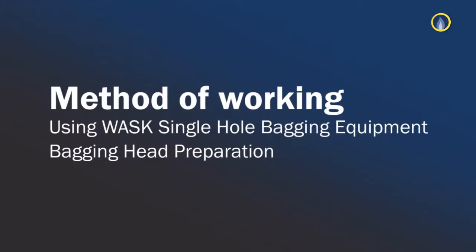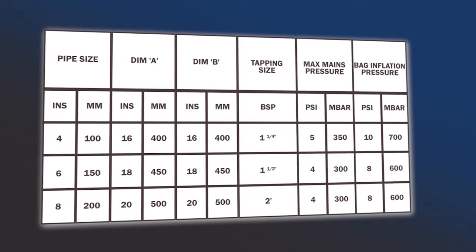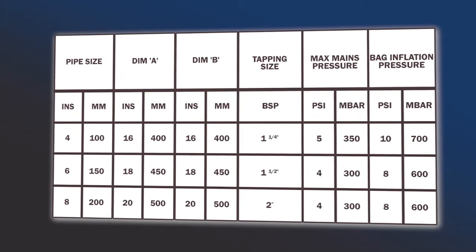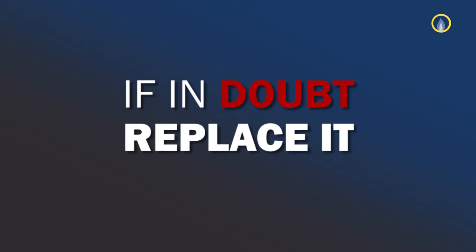Method of Working using WASK Single Hole Bagging Equipment. Select the correct size of bag for your main size. You'll require five bags for setting up a two-way stop. Ensure that the O-ring is present in the bag connector and is located in the bottom of the thread. At this stage, check the bag used-by date and general condition. If you have any doubt, replace it.